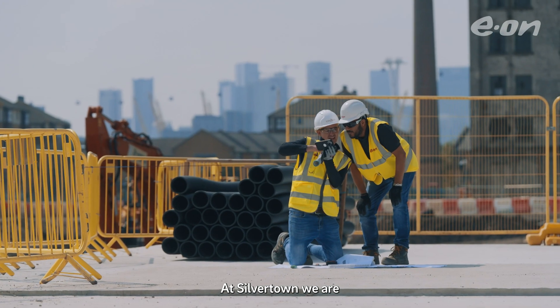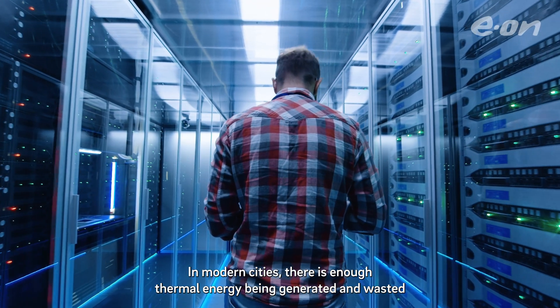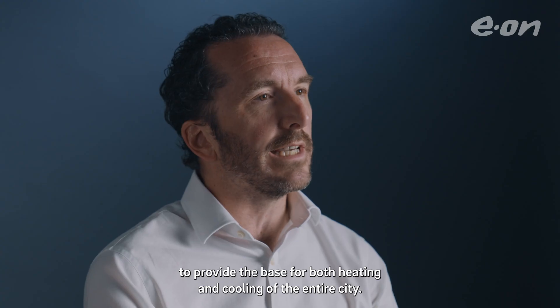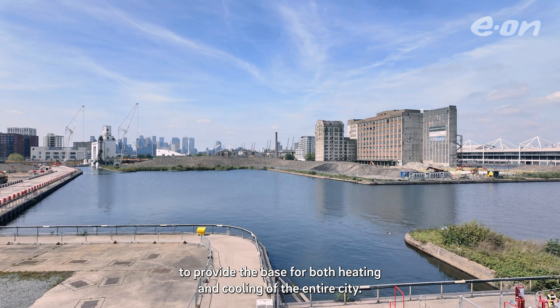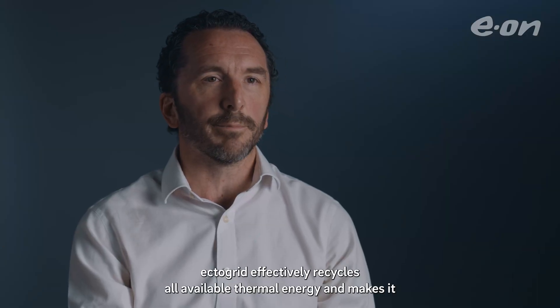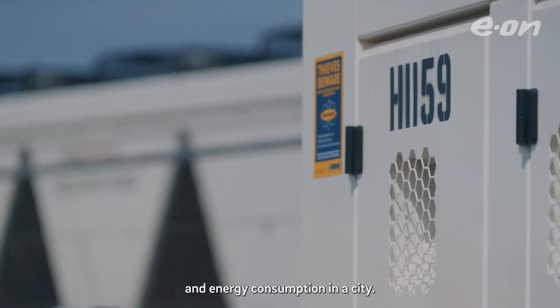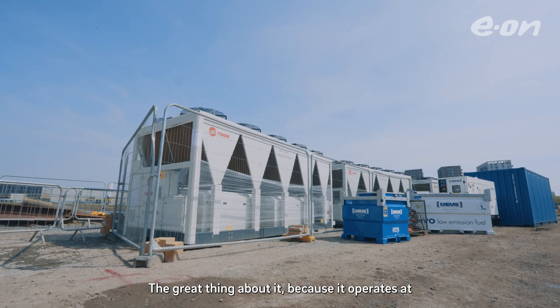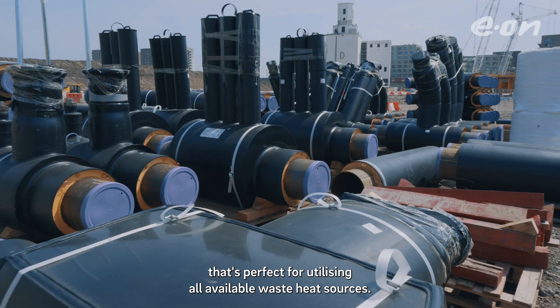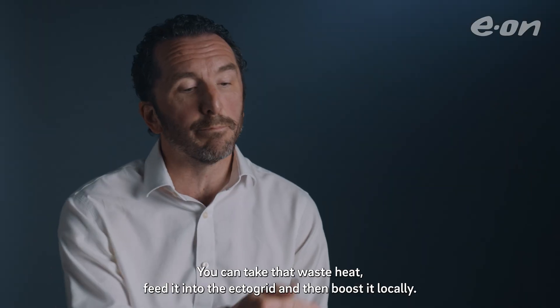At Silvertown we are designing and installing our first EctoGrid in the UK. In modern cities there is enough thermal energy being generated and wasted to provide the base for both heating and cooling of the entire city. EctoGrid effectively recycles all available thermal energy and makes it possible to decrease both pollution and energy consumption in a city. Because it operates at around 20 to 30 degrees, that's perfect for utilising all available waste heat sources — you can take that waste heat, feed it into the EctoGrid, and then boost it locally.